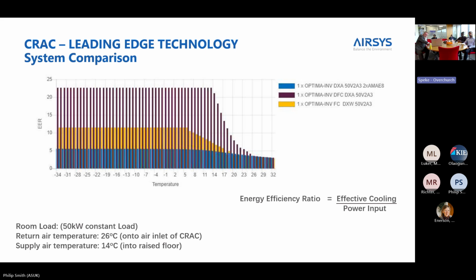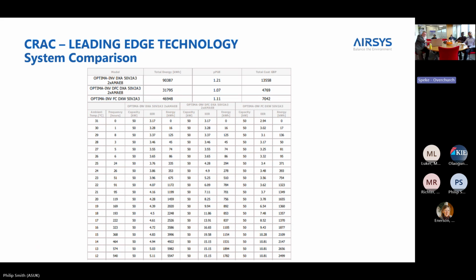But if you then look at the energy cycle, we then viewed the energy that the standard DX, the DX with fresh air free cooling, and the DX water cooled would give. And it's not easy to see, but a standard DX unit, typical PPUE 1.21. If you've got the water cooled, 1.11. If you've got fresh air, 1.07.